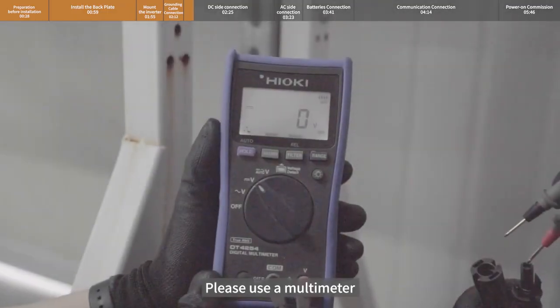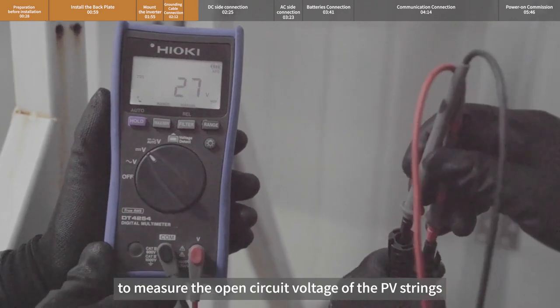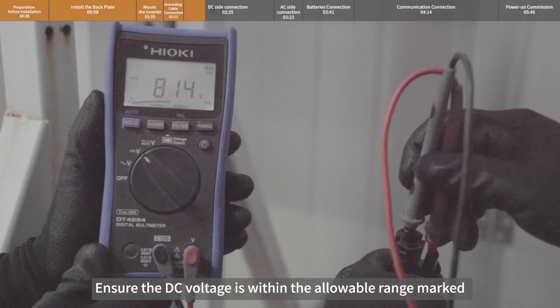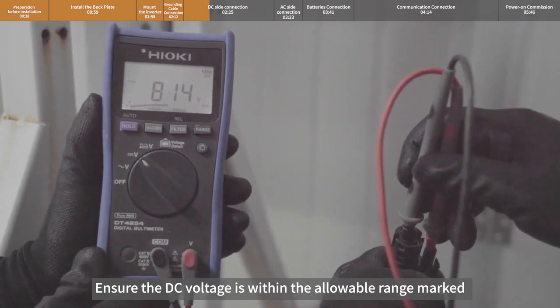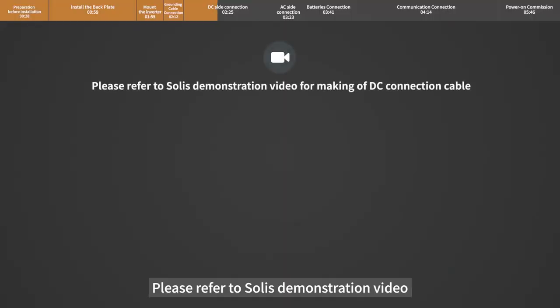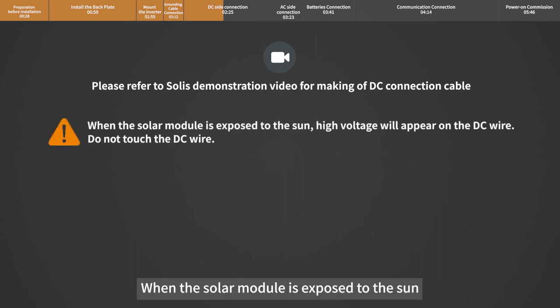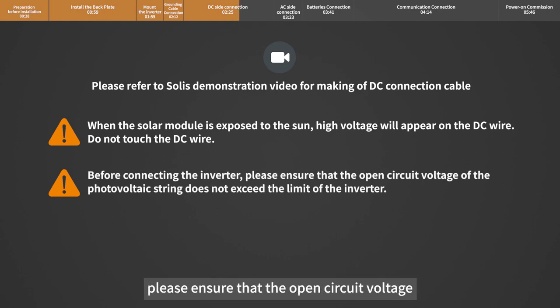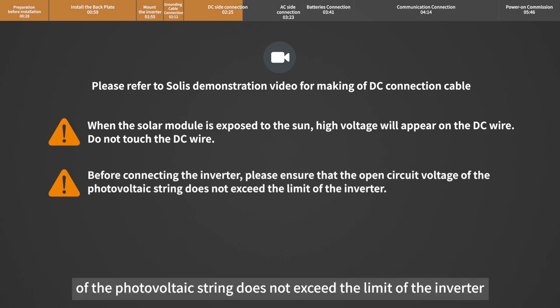Please use a multimeter to measure the open circuit voltage of the PV strings and distinguish the positive and negative poles. Ensure the DC voltage is within the allowable range marked on the nameplate of the inverter. Please refer to Solis demonstration video for making the DC connection cable. When the solar module is exposed to the sun, high voltage will appear on the DC wire — do not touch the DC wire before connecting the inverter. Please ensure that the open circuit voltage of the photovoltaic string does not exceed the limit of the inverter.